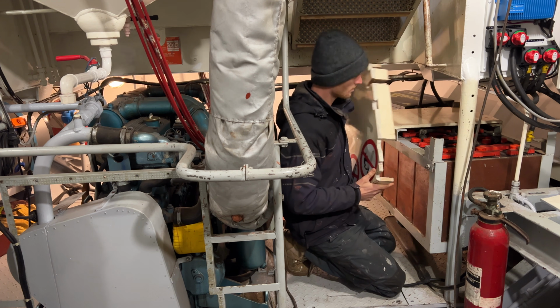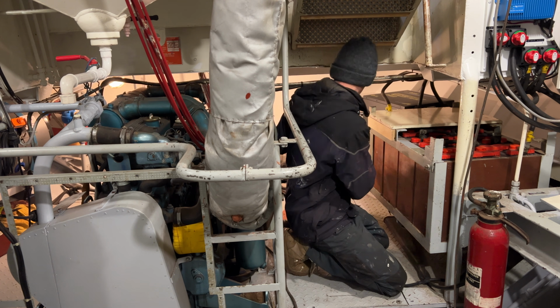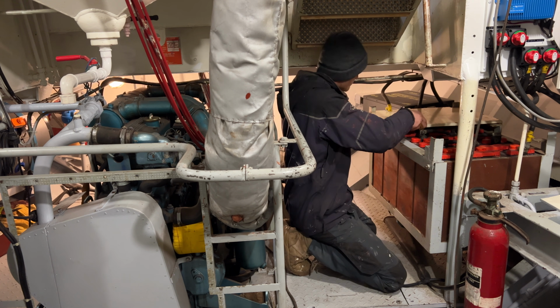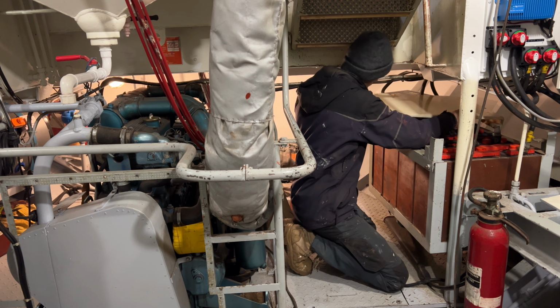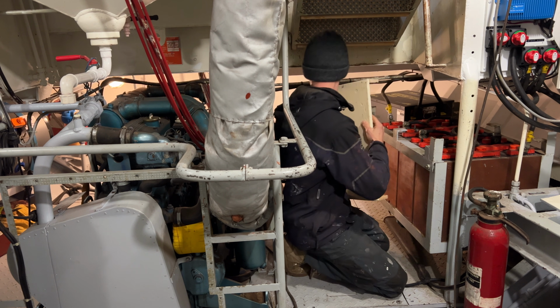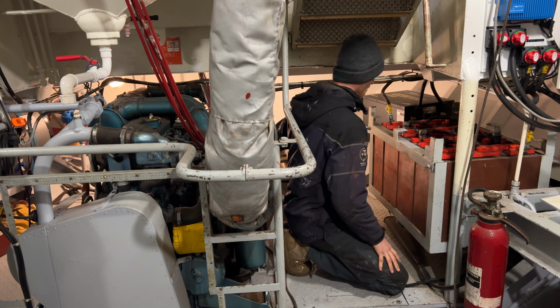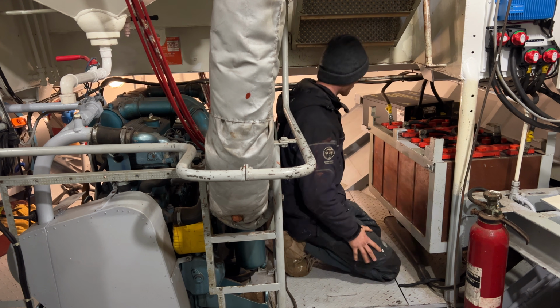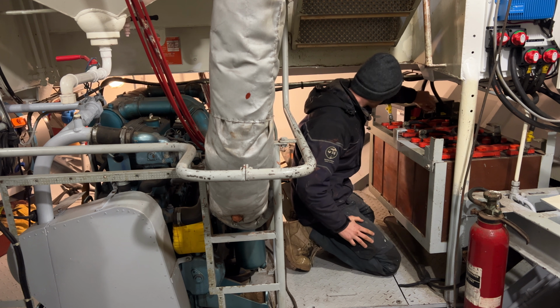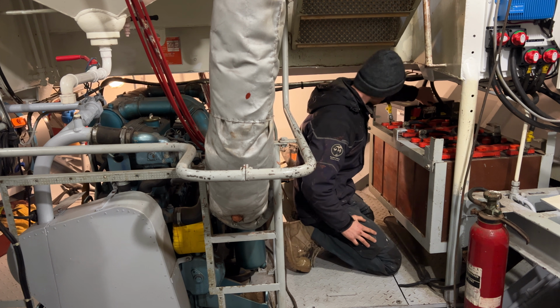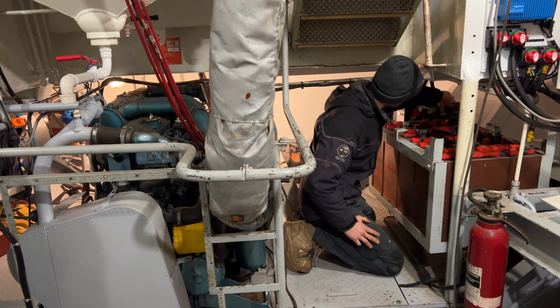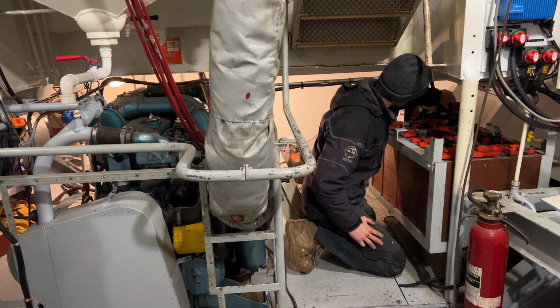However, if something on the old bank breaks again, we still want to be able to start the main engine. So we're going to test a little emergency start procedure using the new LFP battery and some jumper cables. We are doing this with jumper cables instead of a changeover switch because it's only for emergencies.